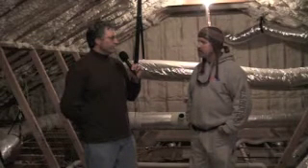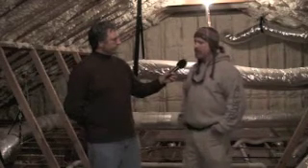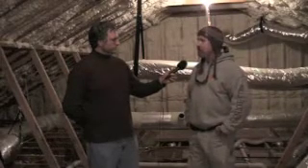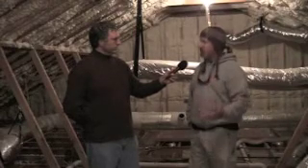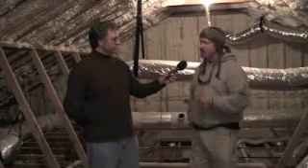So Mills Brothers Heating and Air is taking you approach a project by looking at the house system wide then. Right, building science, if you will, and based off of Manual J through Wrightsoft. They're a company who sells programs to do that, and they look at the house's structure, and as a building science collectively, how will the system work with the house, where it's placed, what city, town, what materials we've used to build it with, windows, down to everything we put in there, how many fireplaces, et cetera. And we really do a pretty good bit of work to get that together, and by the time we're done, over the long haul, it's really accurate.